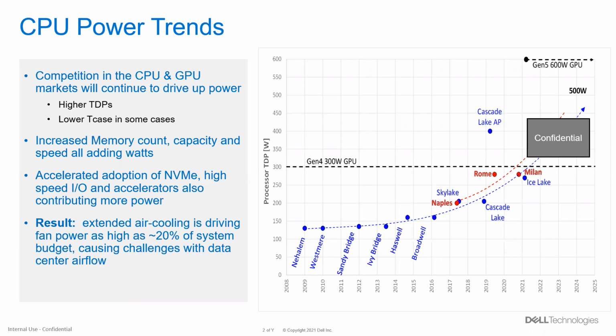So one of the challenges that customers are seeing today and will increasingly see in the future are power trends up and to the right. CPUs in particular, we're seeing CPU TDPs for our current generation approach 300 watts with the Milan and Ice Lake processors. Next gen will go even higher. Other components contribute to high system power as well: memory, NVMe drives, and particularly the increasing use of GPUs. The result of having higher component and overall system heat is that for air-cooled systems, the fan power associated with moving enough air to cool these can reach as high as 20% of the total system power budget.